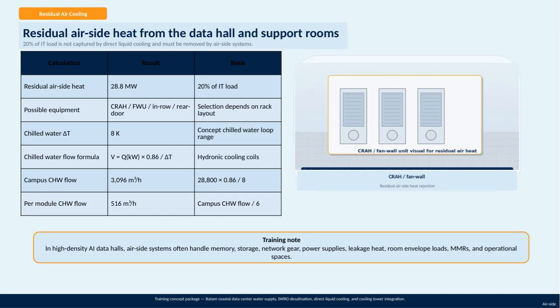Here, we're focusing on residual air cooling, which deals with the portion of heat that isn't captured by direct liquid cooling. Specifically, about 20% of the IT load generates residual airside heat that must be managed via airside cooling systems. This residual heat, calculated at 28.8 megawatts, comes from various sources such as memory, storage, network equipment, power supplies, leakage heat, and even the room envelope itself, including maintenance and operational areas. In high-density AI data halls, these airside systems play a crucial role. The equipment used for this purpose can vary, including CRAH units, fan walls, in-row cooling, or rear door heat exchangers. The choice depends heavily on the rack layout and the specific cooling needs of the space.